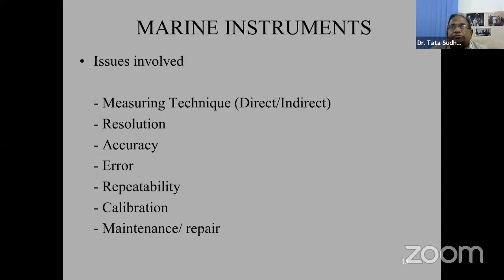And calibration is needed because all the materials are going to drift. The sensor we are using is basically some sort of material which has some properties, and it will have a drift over the years, over the period. I will go through some of the sensors we put in the ocean. They stay for 1 to 2 years. Normally we put them only for 1 year, but because of COVID, we could not go back and recover some of the buoys. So the sensors are there for 2 years.